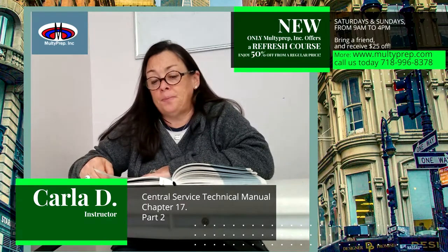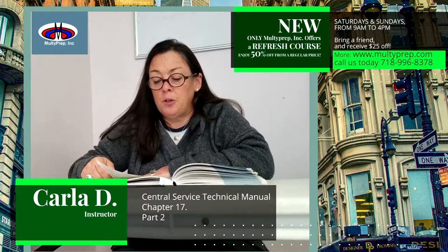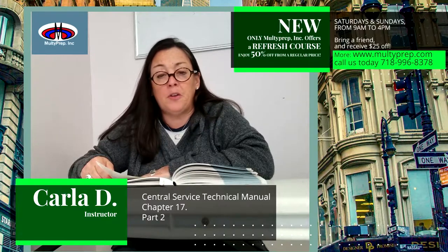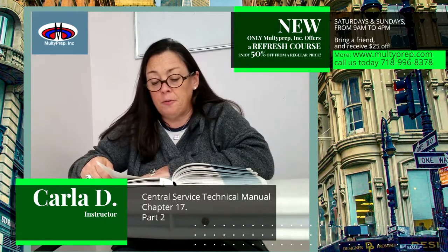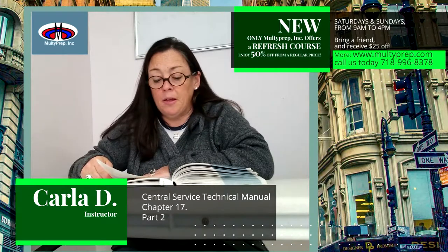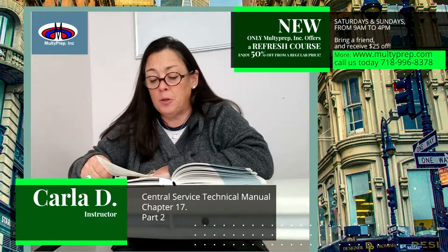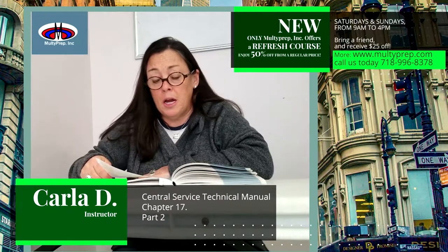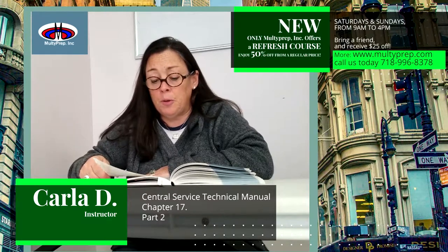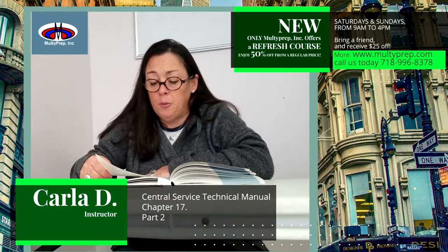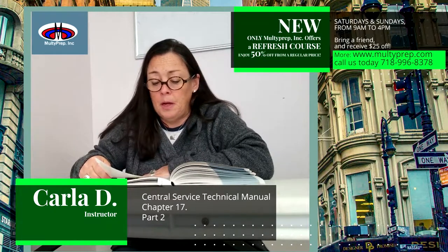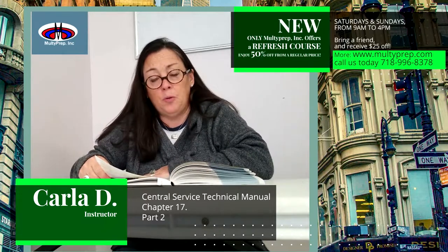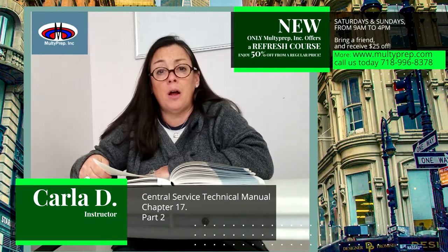Validation and verification. No discussion of sterilization monitoring can be complete without a mention of the validation and verification process. There is a significant difference between validation and verification. Validation is done by the device manufacturer using a documented procedure to obtain, record, and interpret the testing results required to determine a process consistently produces a sterile product. Validation requires extensive laboratory testing and retesting of the process that will be recommended, and the results must be appropriate and reproducible. Testing must also show that the validated sterilization process will not jeopardize the integrity of the product.